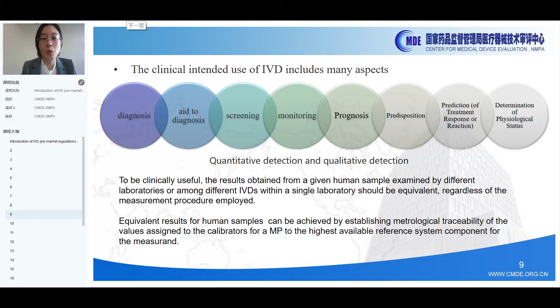To be clinically useful, the results obtained from a given human sample examined by different laboratories or among different IVDs within a single laboratory should be equivalent, regardless of the measurement procedure employed. In addition to the robustness of product quality and the reliability of laboratories and operators, as far as the design of the product is concerned, traceability is a very important factor that affects the equivalence of results. As stated in ISO 17511, equivalent results for human samples can be achieved by establishing metrological traceability of the values assigned to the calibrators for MP to the highest available reference system components for the measurand.